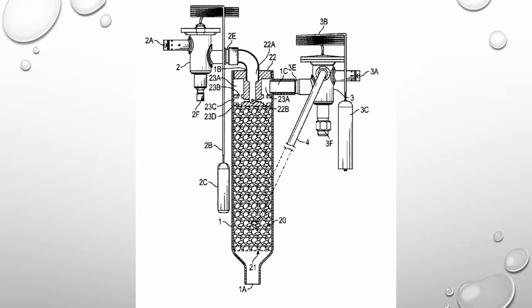The 3C, that bulb is not a sensing bulb, it's a reservoir. It can be fastened to anything except for something that gets extremely hot, like a hot gas line. But a lot of times on an external equalizer, which is the 4, that's where we put it. On the 410-1, it does not have an external equalizer. So I recommend that you put some silicone on above it, take a tie wrap, and just tie wrap it right to the top of the valve.